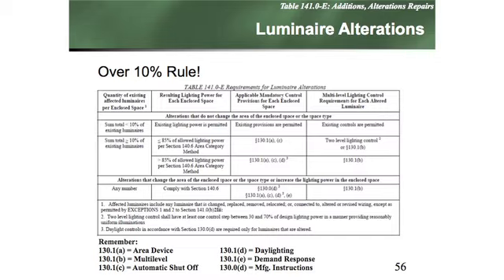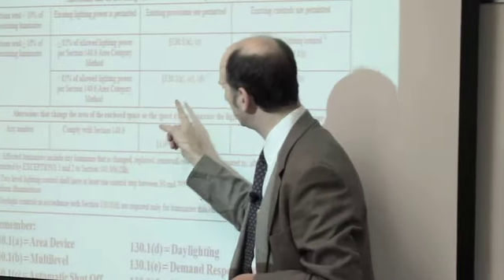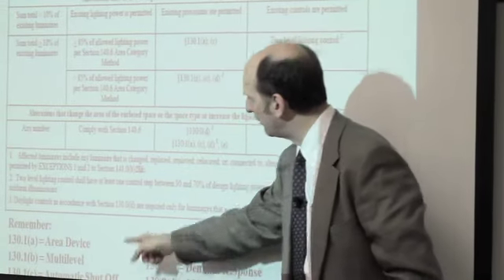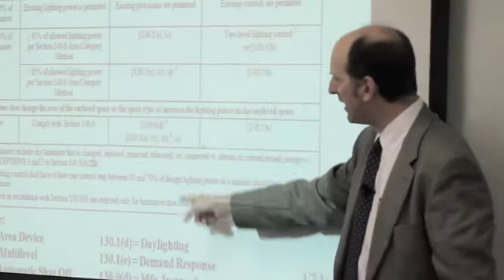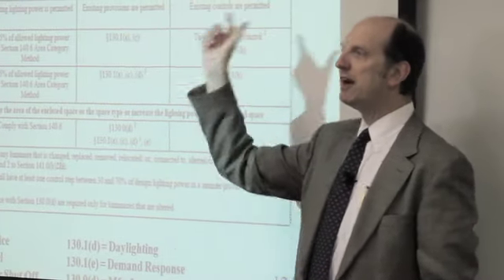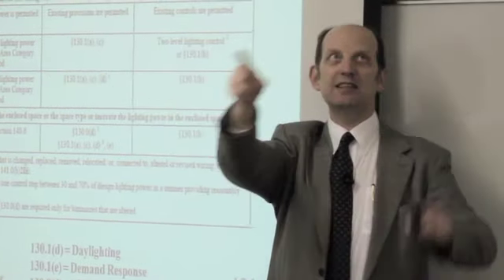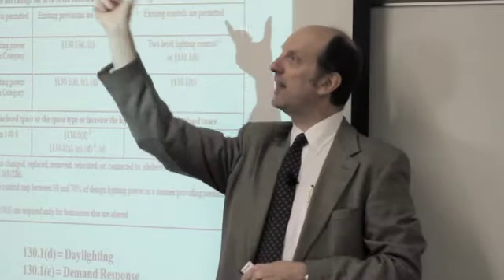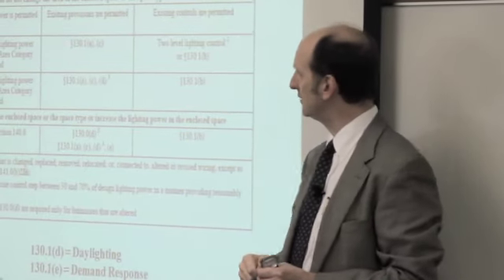...doesn't make it less than 85% of what the area approach allows you to use, they say here we've got the area approach, the area device, the switch in the space, we've got the shutoff, and we've got daylighting as a requirement now for any fixtures in the daylit zone. So if I touch these 2 fixtures, I've got to put daylighting in for the daylighting fixtures.